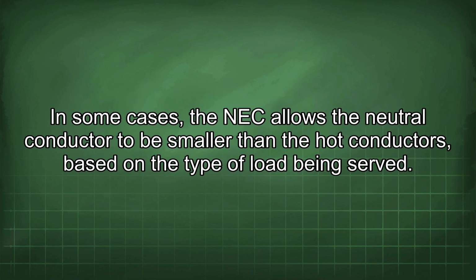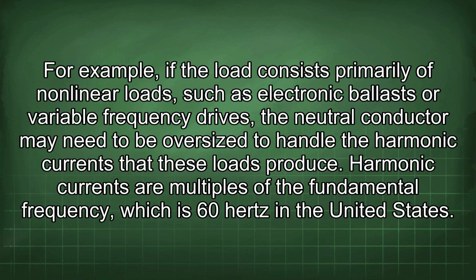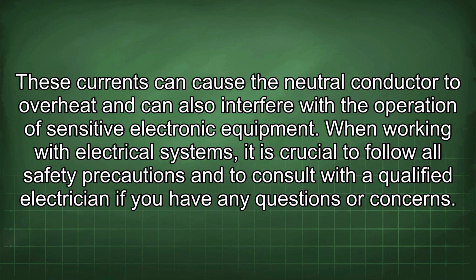One important aspect of neutral conductor sizing is the concept of neutral current reduction. In some cases, the NEC allows the neutral conductor to be smaller than the hot conductors based on the type of load being served. For example, if the load consists primarily of nonlinear loads such as electronic ballasts or variable frequency drives, the neutral conductor may need to be oversized to handle the harmonic currents that these loads produce. Harmonic currents are multiples of the fundamental frequency, which is 60 Hz in the United States. These currents can cause the neutral conductor to overheat and can also interfere with the operation of sensitive electronic equipment.